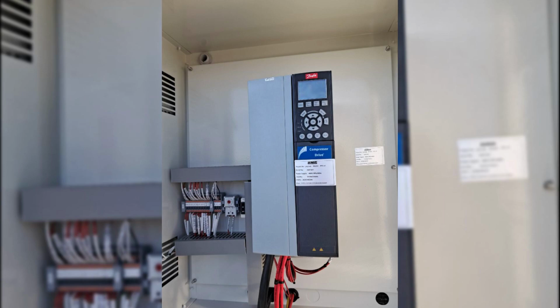Variable frequency drives, VFDs, provided by the packaged pumping manufacturer, must be factory-tested solid-state drives with built-in BACnet MSTP cards. Features: 0 to 100% speed control, automatic reset, current limiting, and PI control. Sleep mode, to shut off pumps during low demand, saving energy. Local, remote operation with hand-off-auto selector. Full diagnostic capabilities: alarms, runtime meters, kWh monitoring. Total harmonic distortion must not exceed 5%, per IEEE 519. Approved VFD manufacturers: AB, Siemens, Danfoss, Yaskawa, GE Fuji, Square D, Vacon.